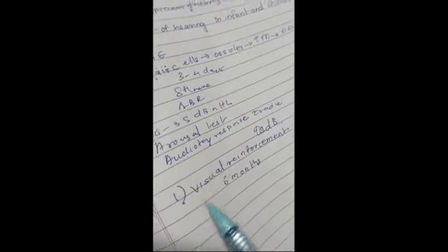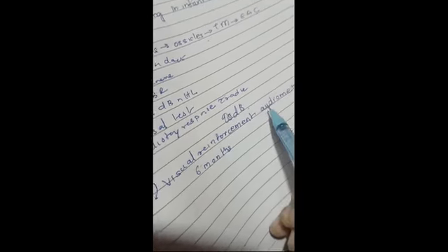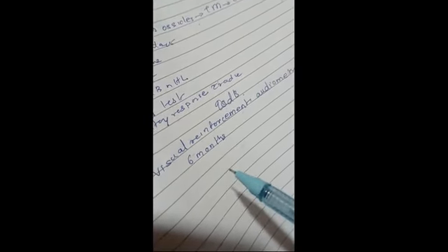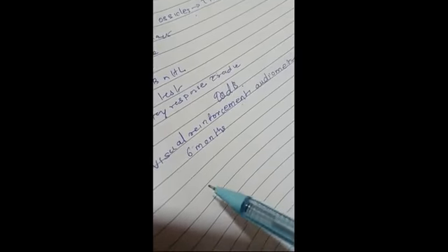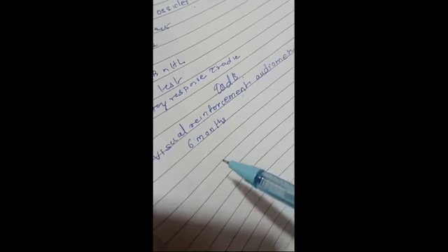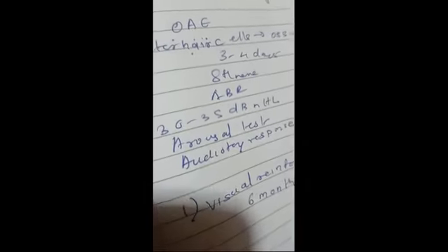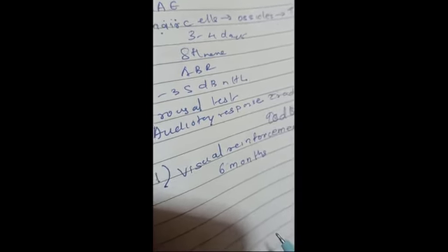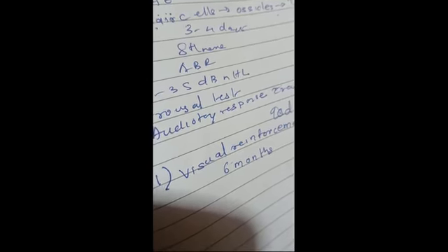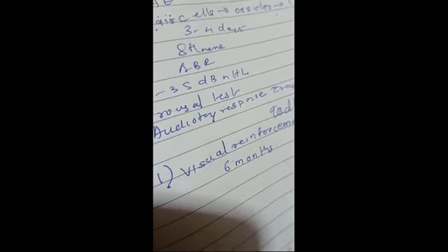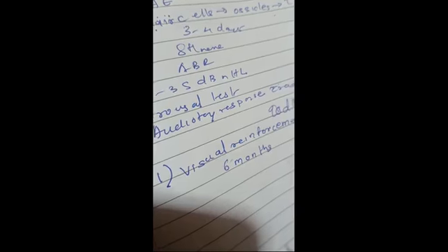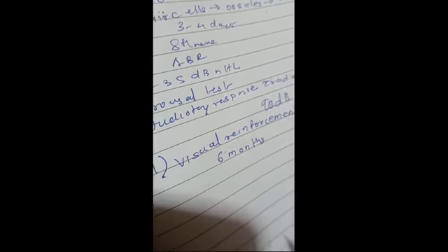Now about conditioning technique. First we discuss visual reinforcement audiometry. Basically, it is a conditioning technique in which the child is trained to look for an audiometric stimulus by turning his head, and this behavior is reinforced by a flashing light on an animated toy, and thus the test helps determine the hearing threshold using standard audiometric technique. The auditory stimulus is delivered by headphone, or better still by insert earphones, which are accepted better and are also lightweight. The test is well suited between the developmental age of 6 months and 2 years.